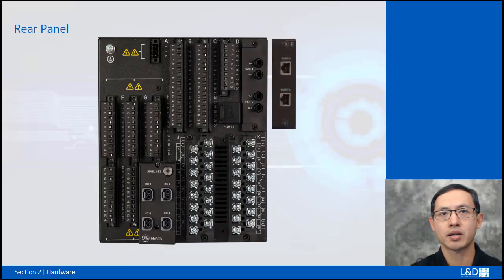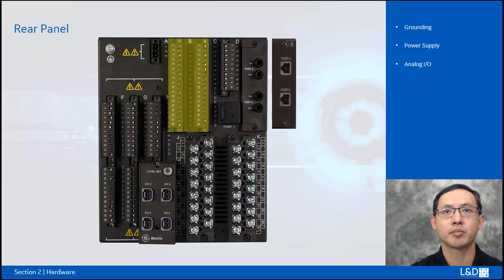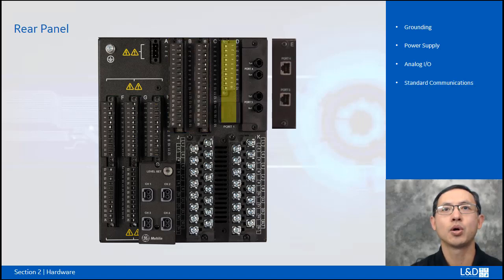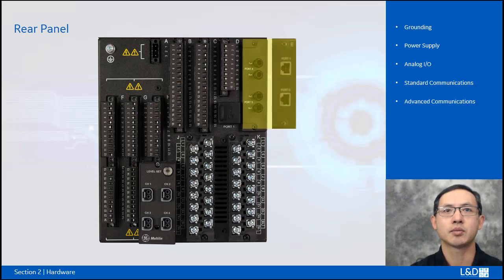On the rear side of the relay, there's 1 grounding screw, power supply unit, analog I/O for the RTDs, standard communication with serial and RJ45 port, advanced communication with 2 fiber optical ports or 2 copper ports. Digital I/O is at the bottom left side with DCMA and arc flash sensors.